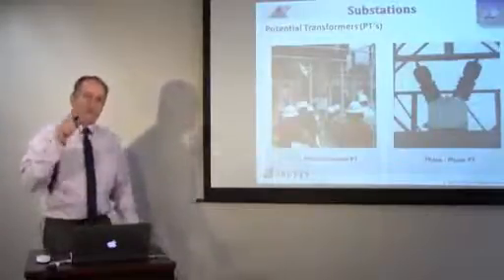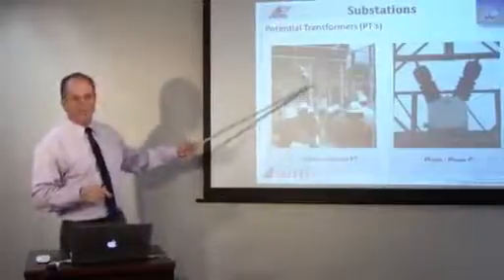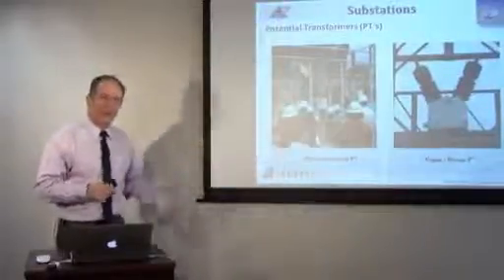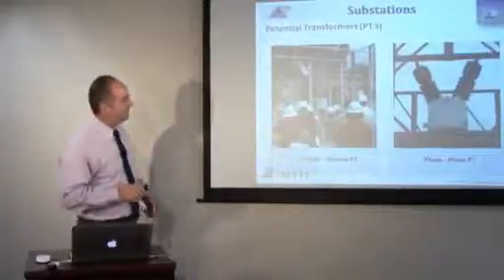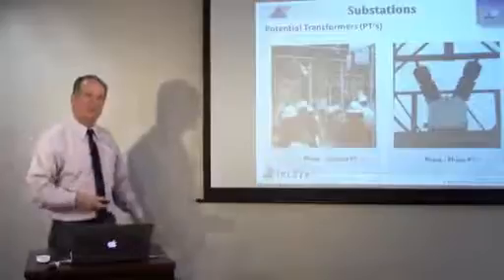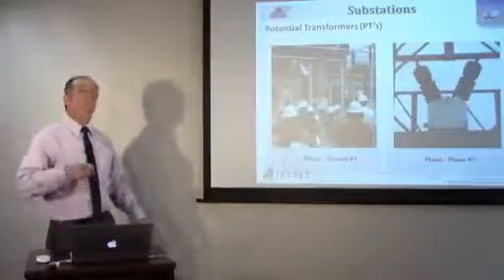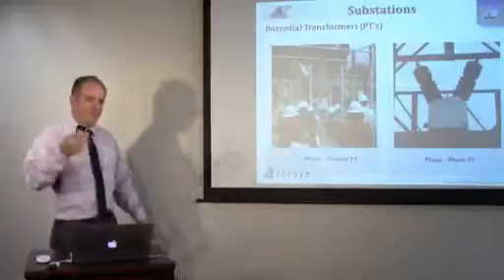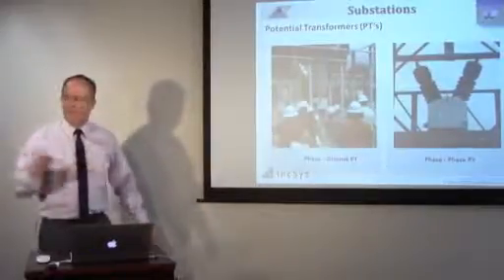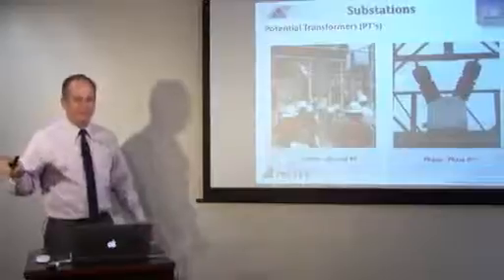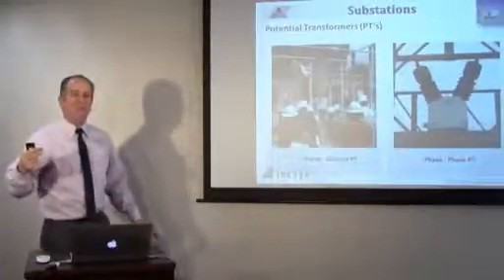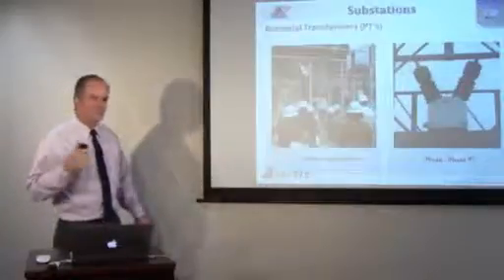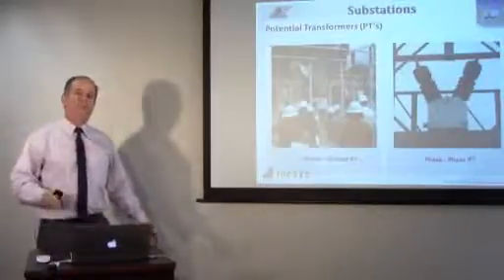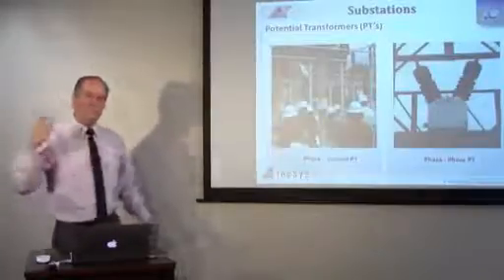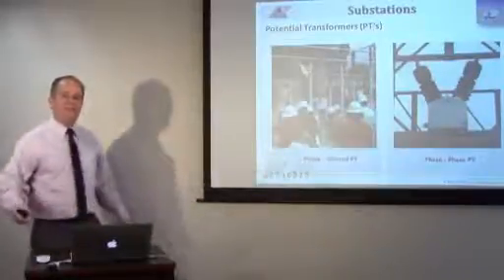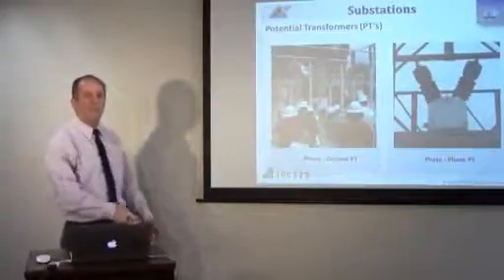So when you're looking at that number on the screen, picture it coming from the actual substation PT or CT. Okay? So that information is really coming from the real world, scaled down through PTs, CTs, transducers, communicated as binary numbers back to the System Control Center through communication circuits, which we'll talk about later, and then converted back to real numbers and displayed on the screen. You're going to see the same thing on the simulator. You're going to see bus voltages. You're going to see bus voltages collapse. That's what the PTs are telling you. Hey, you're doing something wrong, or you better fix this quick. Okay.